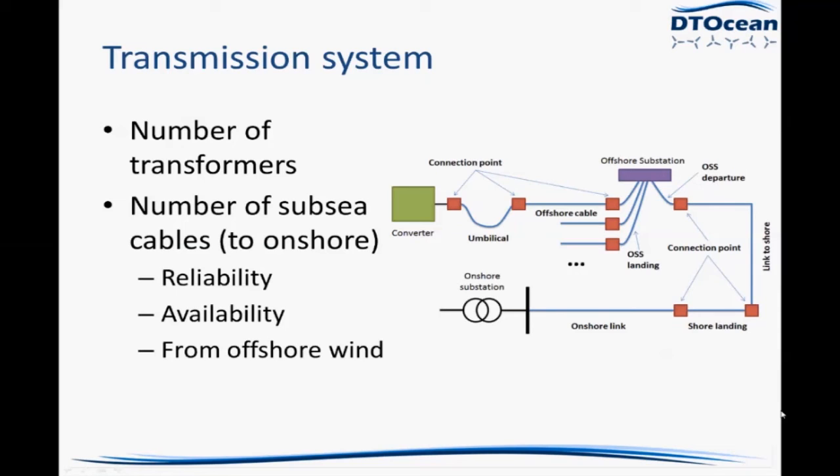They also said another thing: if the size of the farm was greater than, I think, 90 megawatts, then you would need to have two transformers. Now, we're only looking at marine wave and tidal farms up to 100 megawatts, which means we're just on the border there. So again, that's something we can choose. We can have two transformers, but we would need to put in cost and see whether that would make economic sense.